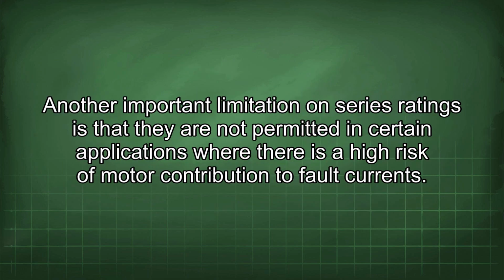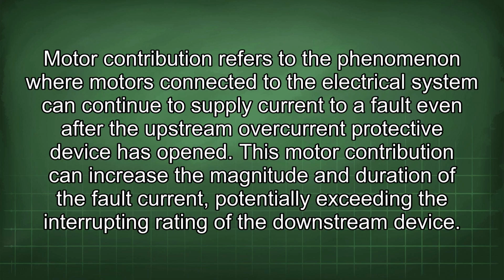Another important limitation on series ratings is that they are not permitted in certain applications where there is a high risk of motor contribution to fault currents. Motor contribution refers to the phenomenon where motors connected to the electrical system can continue to supply current to a fault even after the upstream overcurrent protective device has opened. This motor contribution can increase the magnitude and duration of the fault current, potentially exceeding the interrupting rating of the downstream device.